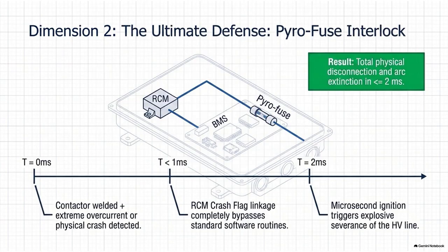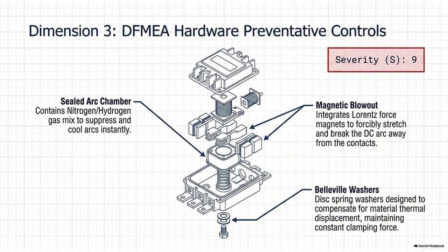The ambient oxygen in the air will actively feed and oxidize the plasma arc, burning the metals faster. Furthermore, ambient humidity, the water vapor in the air, significantly lowers the electrical resistance of the gap, making it much easier for the arc to strike and sustain itself. So just normal air is the enemy here. It is. Yeah. Therefore, a true ASIL-D rated high-voltage relay is never exposed to the atmosphere.